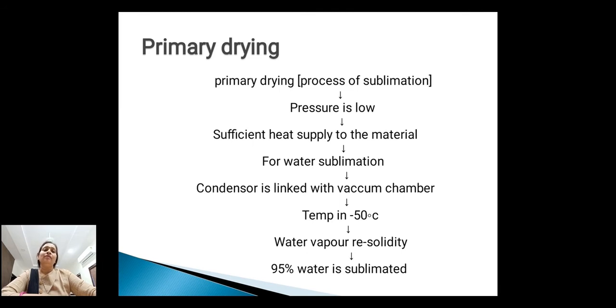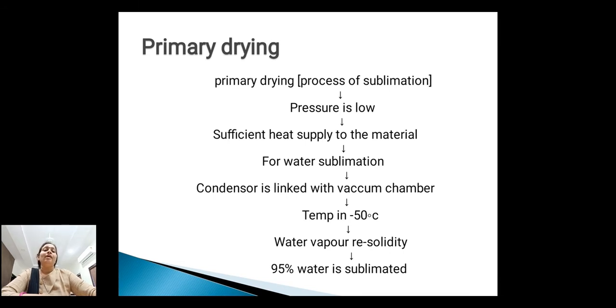Next, primary drying. Primary drying process is also known as sublimation. In this process pressure is low and sufficient heat is supplied to the material. For water sublimation, a condenser is linked with the vacuum chamber and at that time the temperature is minus 50 degrees centigrade. Water vapor is also re-solidified. At the end of this process, 95 percent of water is sublimated from the material.